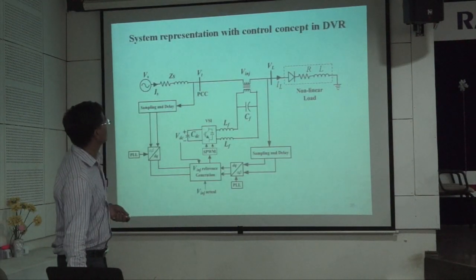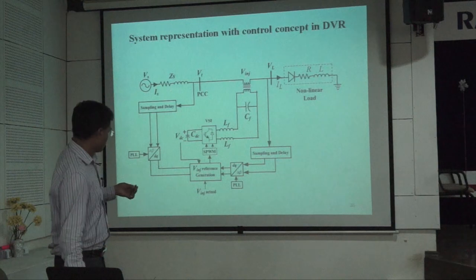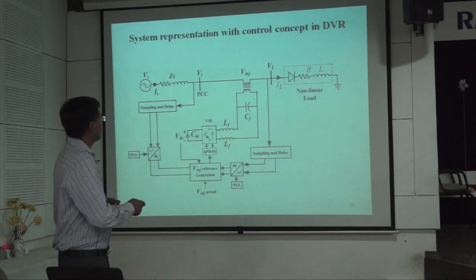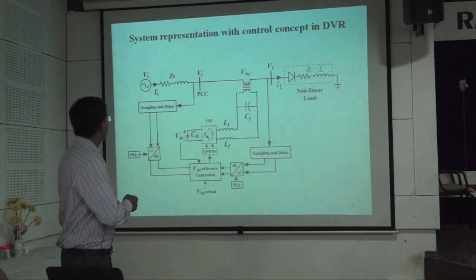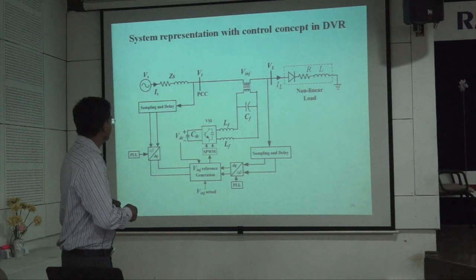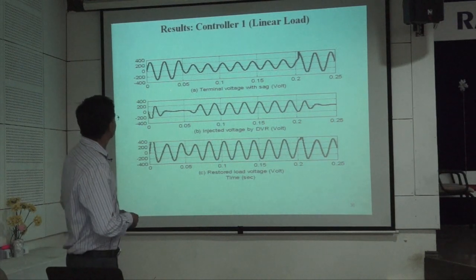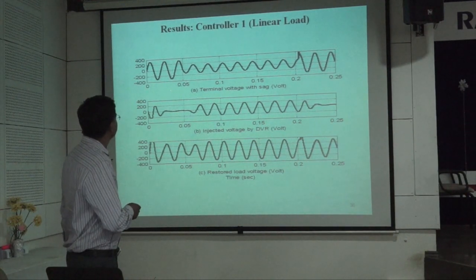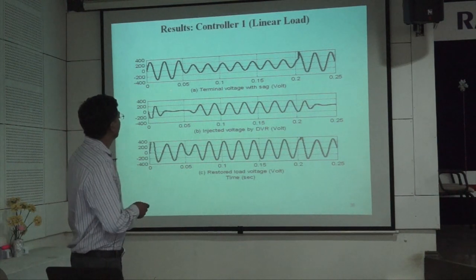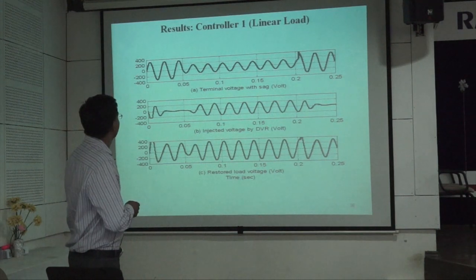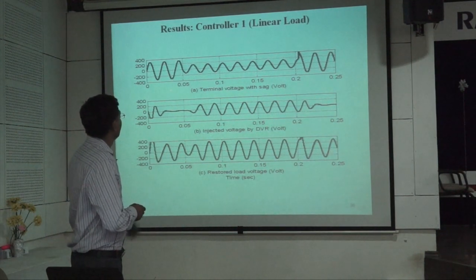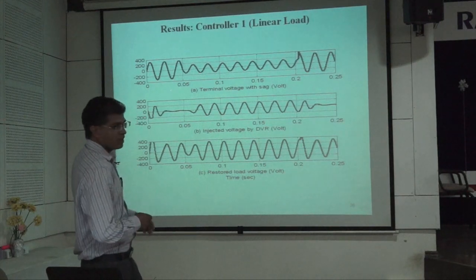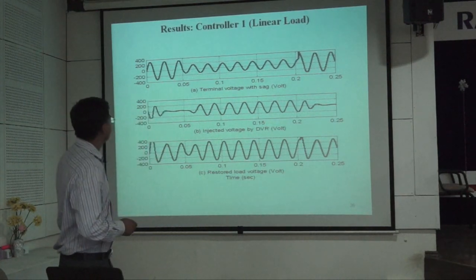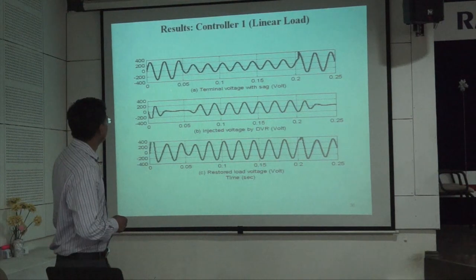This is the system representation with control concept and DVR. Here I need three values: sampling and hold of the terminal voltage, load voltage, as well as DC voltage. These are the results. The sag is created at 0.05 second for near about 6 to 7 cycles. This is a single phase fault, and here near about 55% voltage sag is created by 1 ohm fault resistance, and this is the injected voltage by the DVR.